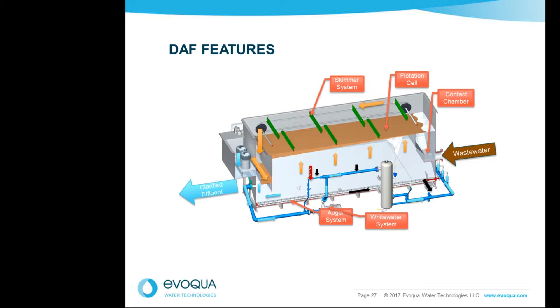Contrary to popular belief, not everything floats — lots of things will settle. So DAFs have a mechanism to handle settled material, either a hopper in the bottom with drain ports, or in this case an auger that pulls the material as it settles to the bottom toward the front end of the DAF, where it is discharged through a port and a blowdown scheme.